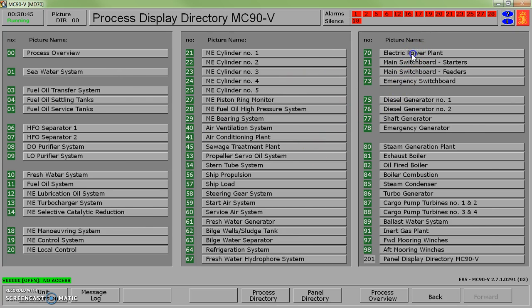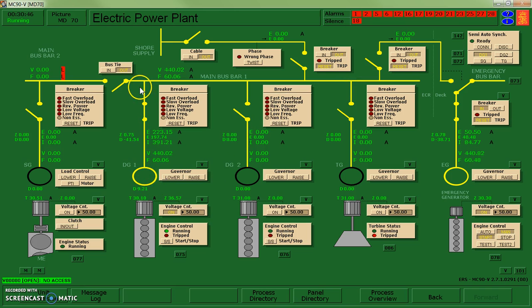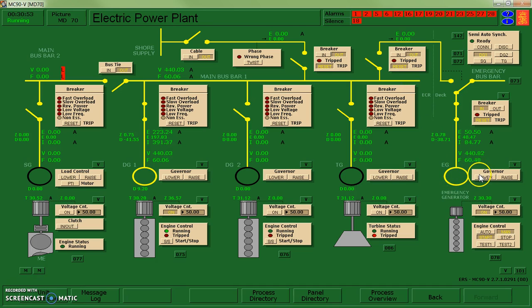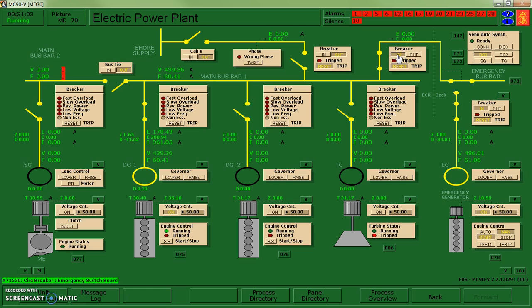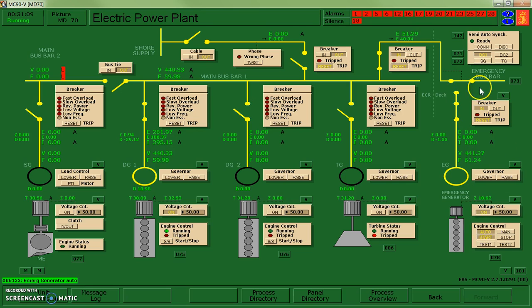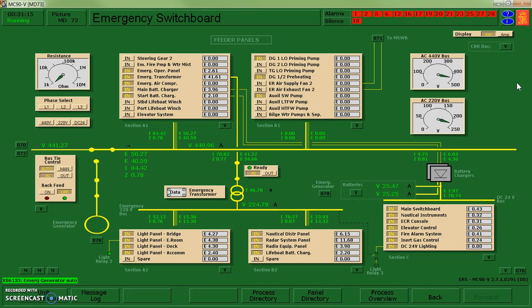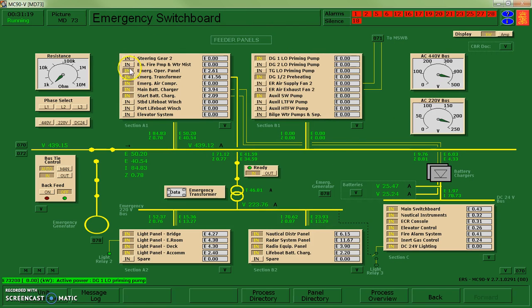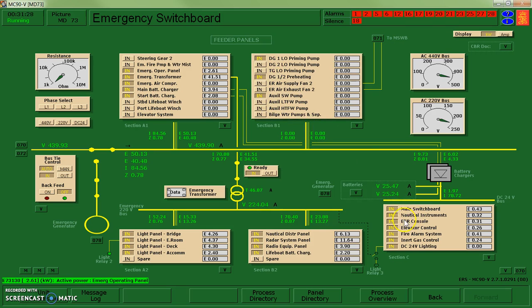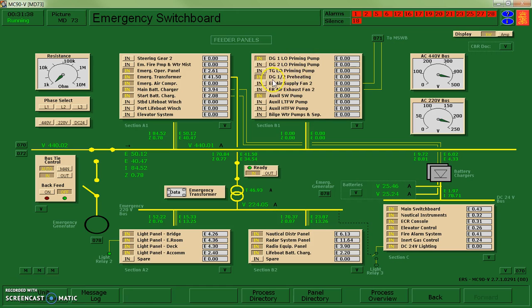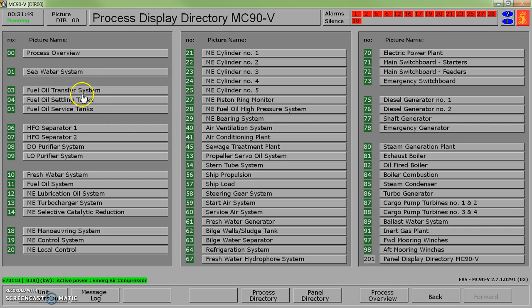My electric power plant - I have one diesel generator that's supplying power to run all those devices. My emergency generator is on still. I could eventually switch it out if I would like to. I can switch in my breaker which will affect my emergency bus bar, and I can switch this guy to auto so he will automatically shut down. One of the issues that happens right when I switch over the electrical supply is that anything that was on in the emergency switchboard might be affected. A couple things that were affected by the emergency switchboard were auxiliary seawater pump, diesel generator lube oil priming pump, preheating. We're just going to double check that those systems weren't affected.